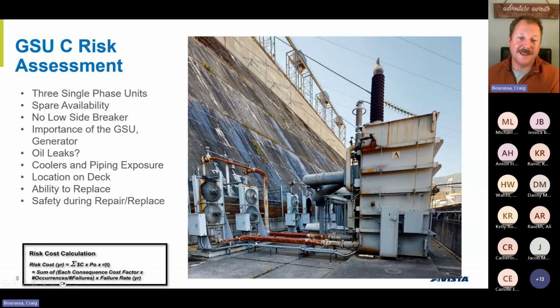But in asset management, you look at all the what-if scenarios. What if there were an oil leak? Here, the probability looks like it could be kind of high due to all this corrosion. So you assess the consequence of having an oil leak that would make it through the sump and go out to the river—that could be maybe a $2 million cleanup effort—and then you assess the probability of that.